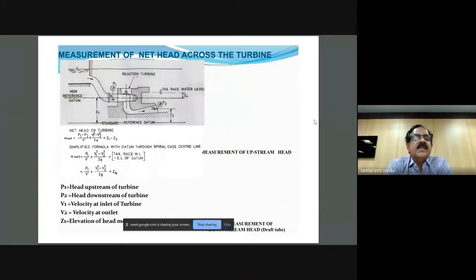Measurement of net head across the turbine, as you know, you are all teachers of fluid mechanics. It is the well-known Bernoulli's theorem, which we can relate to the steady flow energy equation, the steady state energy equation. The net head across the turbine is the difference between these two energies, that is P by gamma plus V square by 2g plus Z, measured at upstream and downstream. Upstream is immediately upstream of the scroll, near the main inlet valve, and downstream point 2 is usually the end of the draft tube, as seen here.